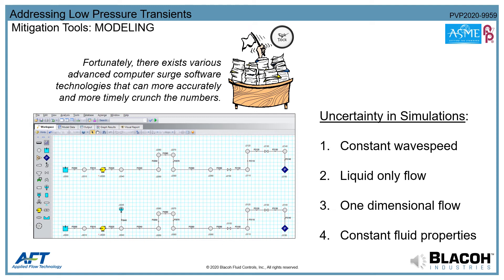Accurately predicting a system's response to cavitation over time requires multi-phase flow models that are exponentially more complex. Fortunately, the onset of cavitation can be predicted very accurately using single-phase computer models, and short-lived small vapor cavities can be considered a local phenomenon where modeling in the liquid-only framework is still quite accurate. It is common good practice to eliminate or minimize cavitation. A substantial body of theoretical research and verification studies show these assumptions are reasonable for the vast majority of engineering purposes.